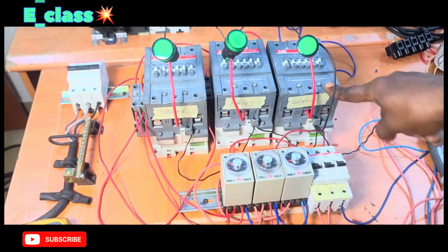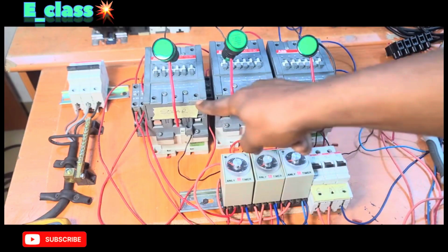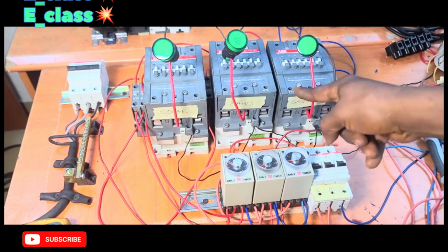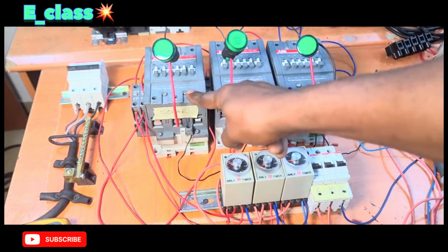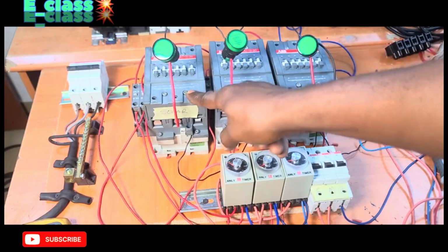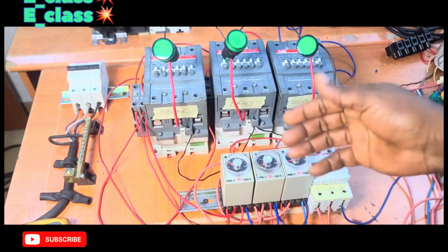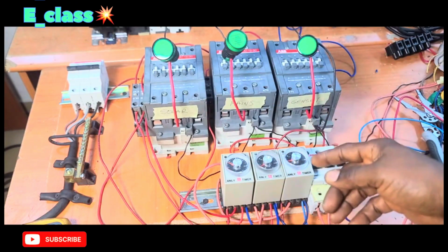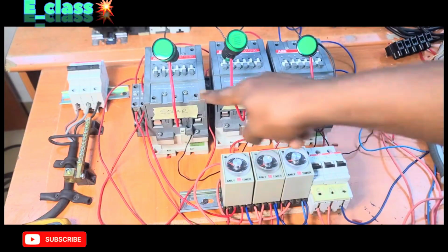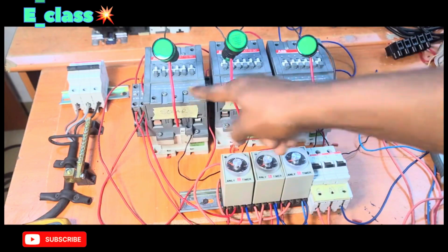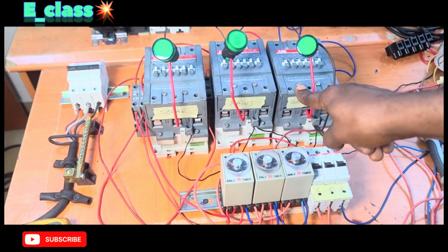If this one is on and solar is restored and active, it's supposed to disconnect this one instantly and delay for some seconds before energizing this one. But I noticed that when this one is on and solar is restored and active, this one does not cut off instantly.